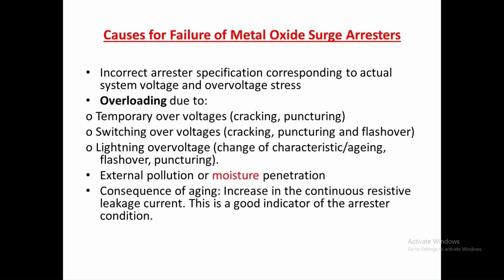And sometimes it also happens that the very protective element, the surge arrestor itself, has failed. That may be due to mechanical stress, temporary over voltages, cracking, puncturing, and flashover, and maybe due to aging or pollution or moisture penetration. So these are the causes which may lead to the failure of the metal oxide surge arresters.